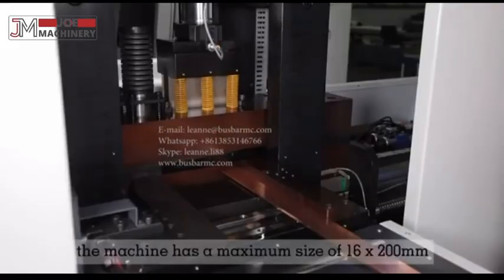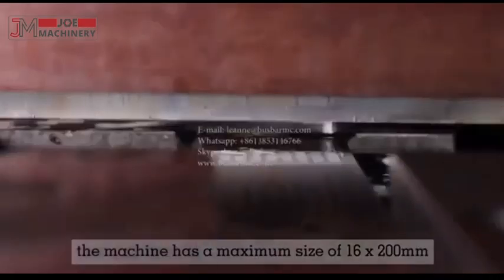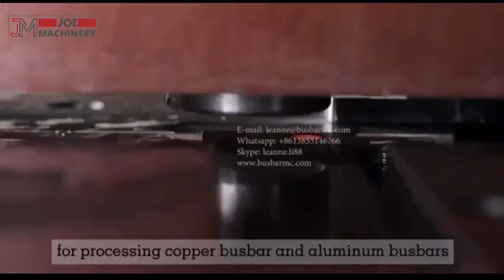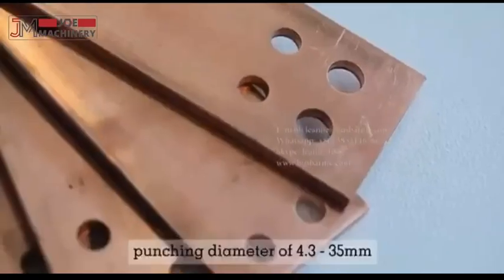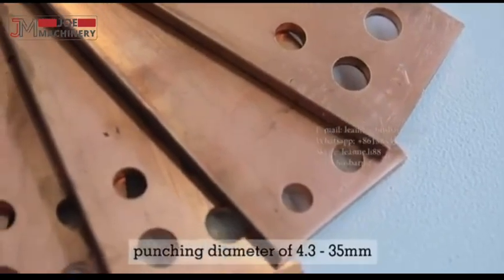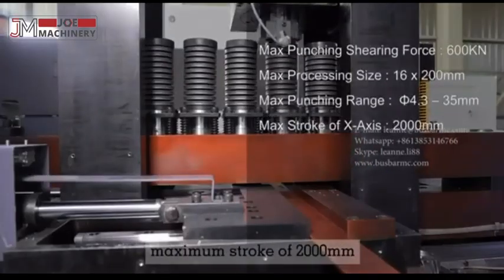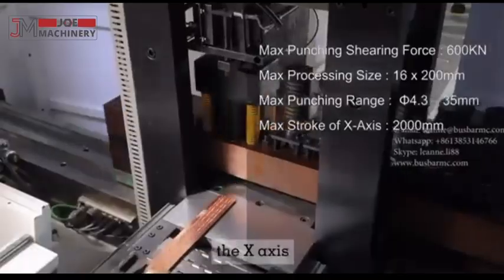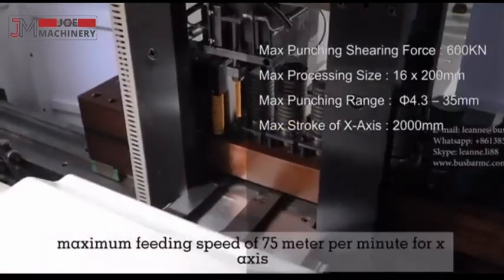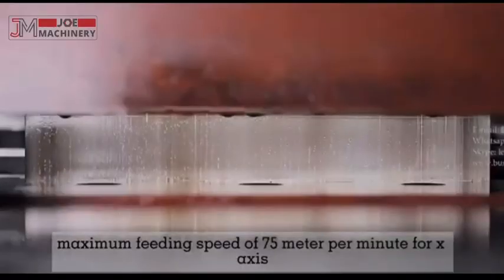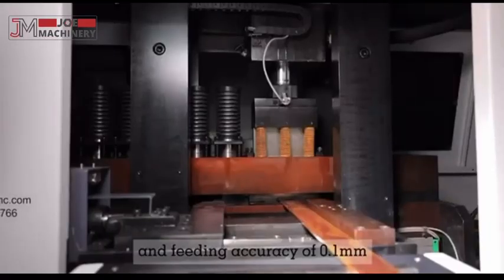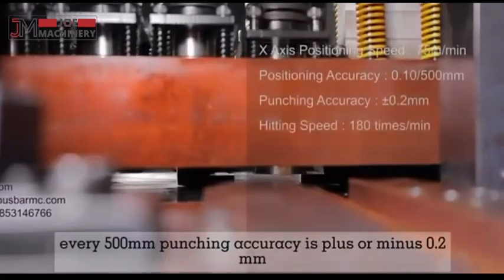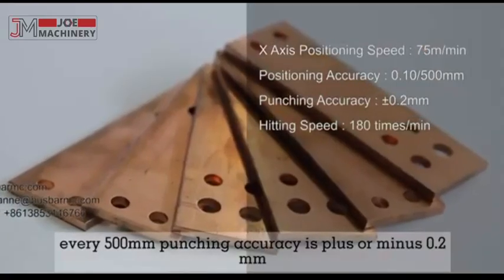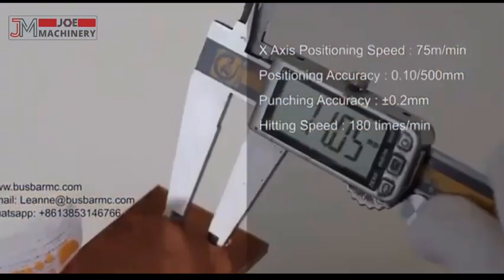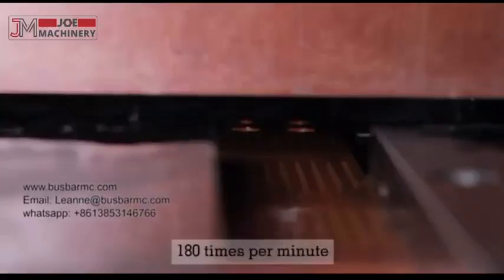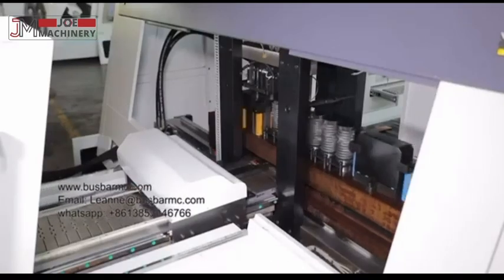The machine has a maximum size of 16 by 200 mm for processing copper busbar and aluminium busbars. Punching diameter of 4.3 to 35 mm. Maximum stroke of 2000 mm for the x-axis. Maximum feeding speed of 75 meters per minute for x-axis. And feeding accuracy of 0.1 mm every 500 mm. Punching accuracy is plus or minus 0.2 mm. And the maximum punching frequency is 180 times per minute.